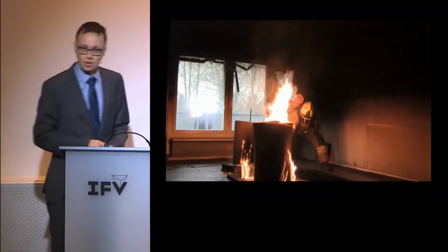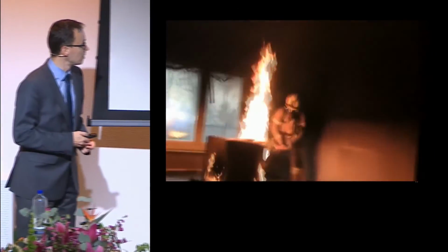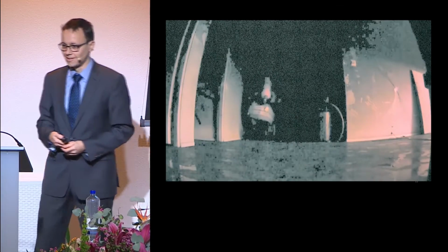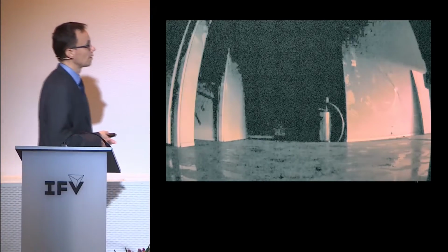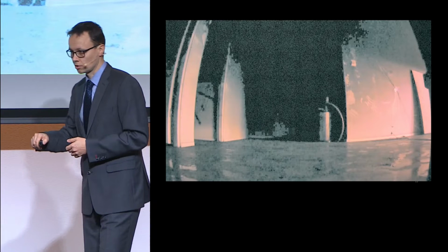This is a test from one of the polyurethane foam tests. Now the fireman who ignited it tries to get out, but he cannot. He cannot pull the door open from the handle. So the fellow workers try to help him and finally manage to open the door. Okay, at the time when he was pulling from the handle, the overpressure in that room was already about 500 Pascal.